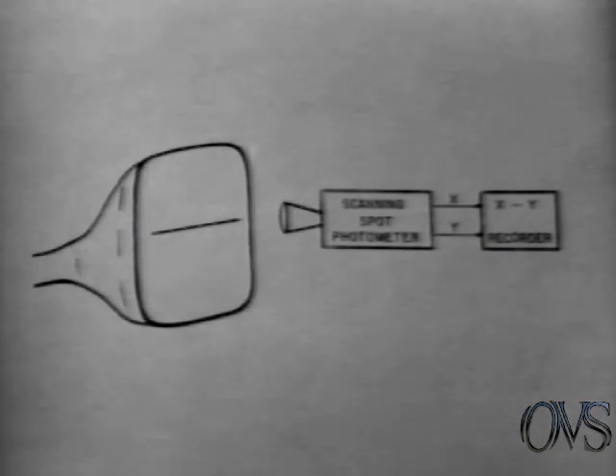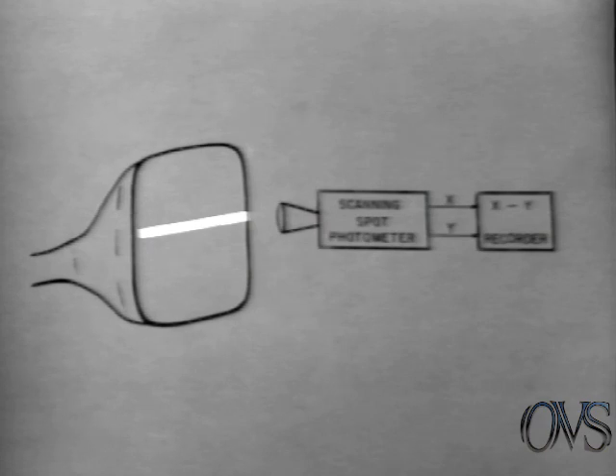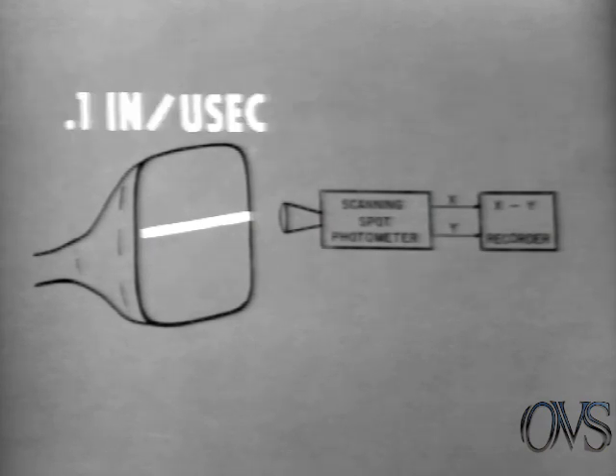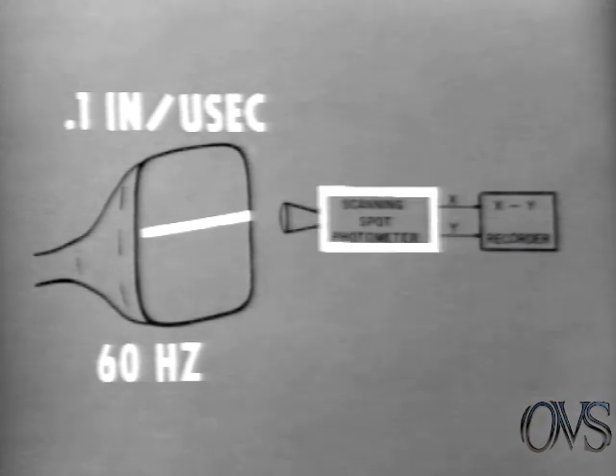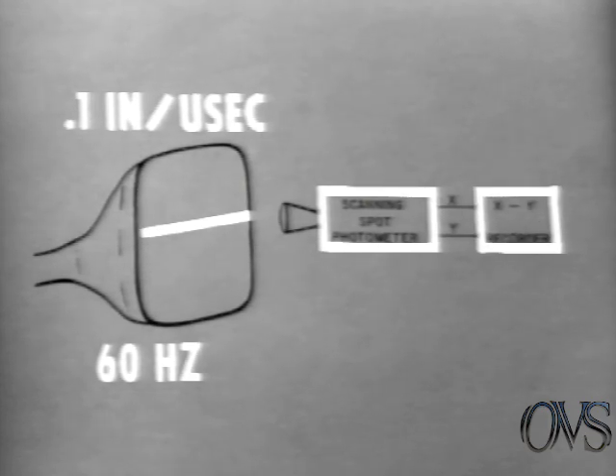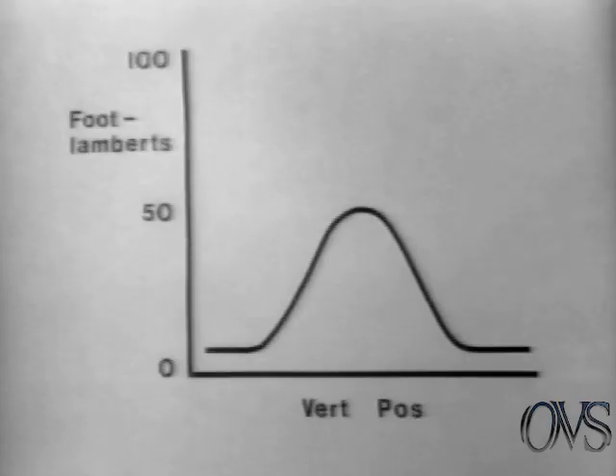The instrument is set up to display a horizontal line at a writing speed of 0.1 inches per microsecond at a 60 Hz refresh rate. A scanning spot photometer is mounted in front of the instrument and is adjusted to scan vertically across the displayed line. The X and Y outputs of the photometer are connected to an XY recorder. The resulting recorder plot will look something like this, with brightness plotted against vertical position.